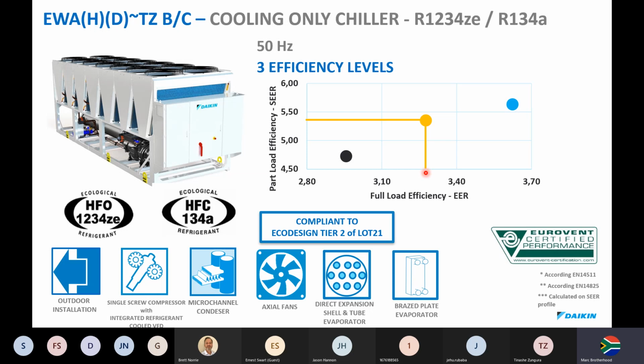I mentioned earlier on, if you've got a process cooling, even with inverter chillers, it's a fine line on the initial design, because inverters use more electricity at full load than a non-inverter chiller, for the simple reason there's a lot of heat generated in the power electronics, as well as the heat of compression. You add those two together, the energy efficiency ratio drops at full load. This only happens at full load. So at full load, an inverter chiller is less efficient. So it's not advisable to select an inverter chiller for a full load operation.